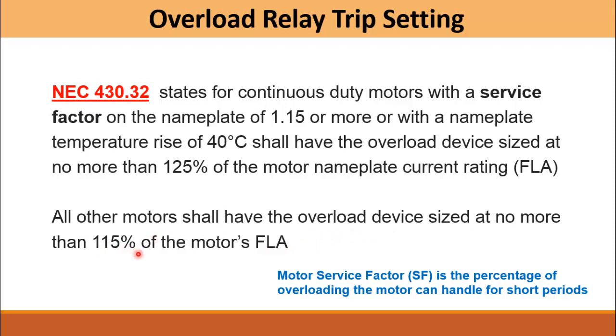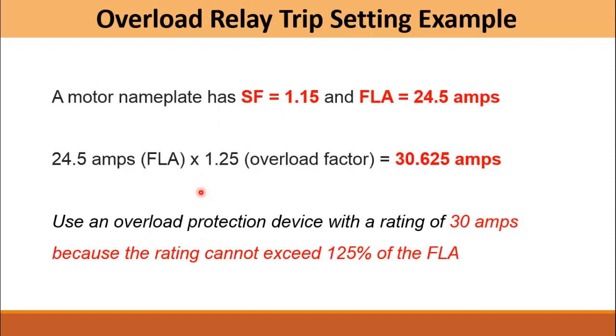To size the overload relay, you first need to check the service factor on the nameplate and the allowable temperature rise, and then set the overload relay accordingly. As an example, consider a motor with a service factor of 1.15 and a full load ampere of 24.5 A.